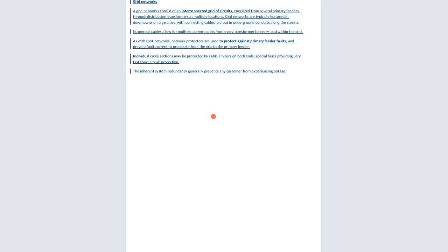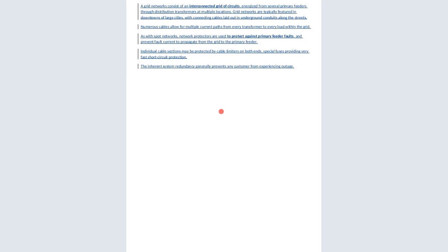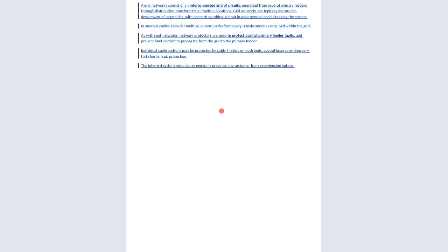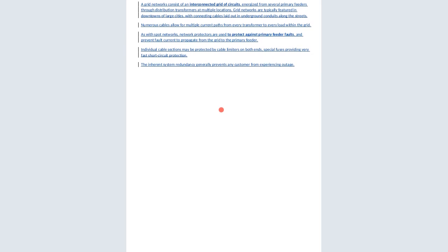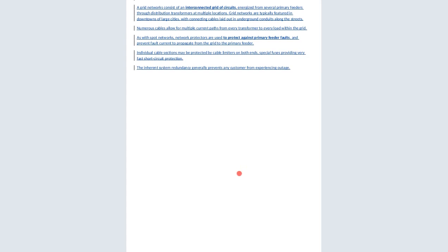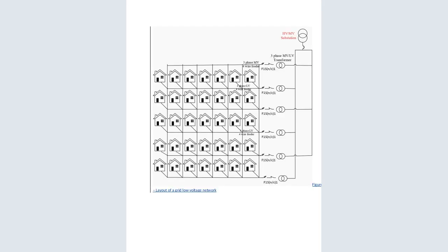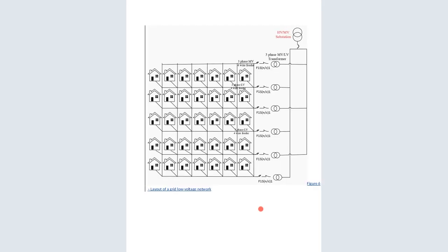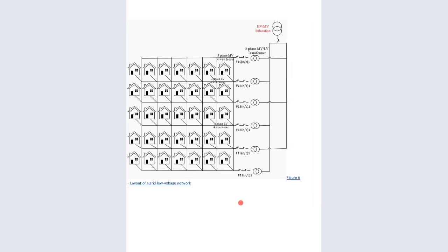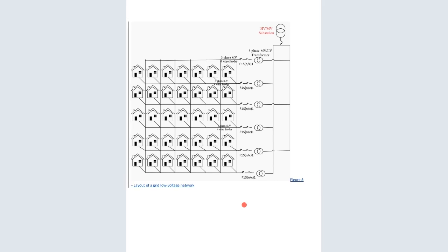Individual cable sections may be protected by cable limiters or both-end special fuses, providing very fast short circuit protection. Inherent system redundancy generally prevents customers from experiencing outages. So you can see the grid voltage networks the way they are. All of them are getting the same power.